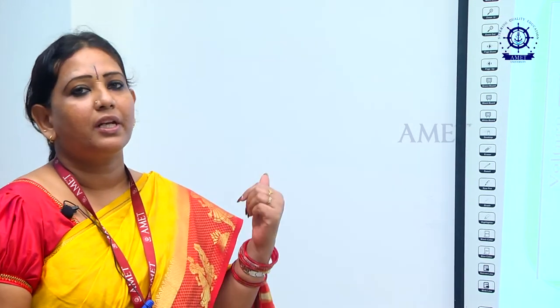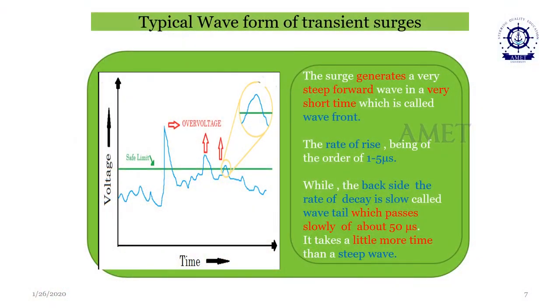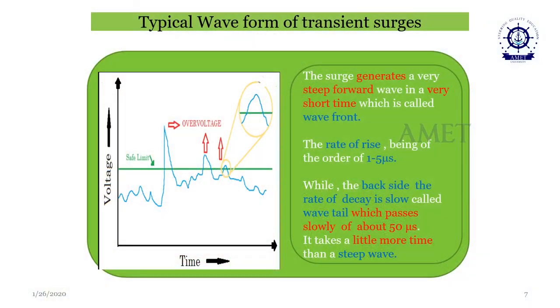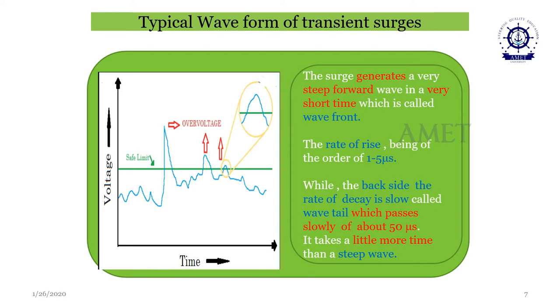Now see, this is the typical waveform of transient surges, shown as time versus voltage. The green line represents the safe limit, which is the normal system voltage. Suppose, due to man-made operations or a natural phenomenon like lightning, there will be an elevation of voltage generated in the power system network. It can be on the generation side, the transmission side, or the distribution side. You can see there is a sudden, sharp rise of overvoltage in the power system, shown as an overvoltage with a marked arrow.